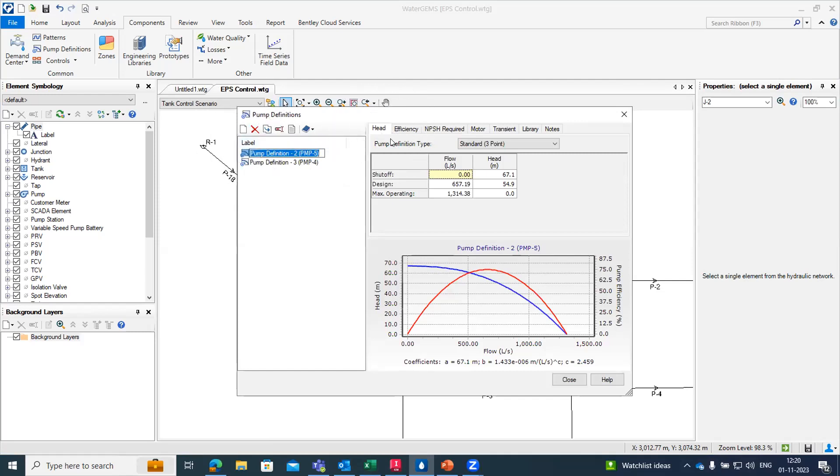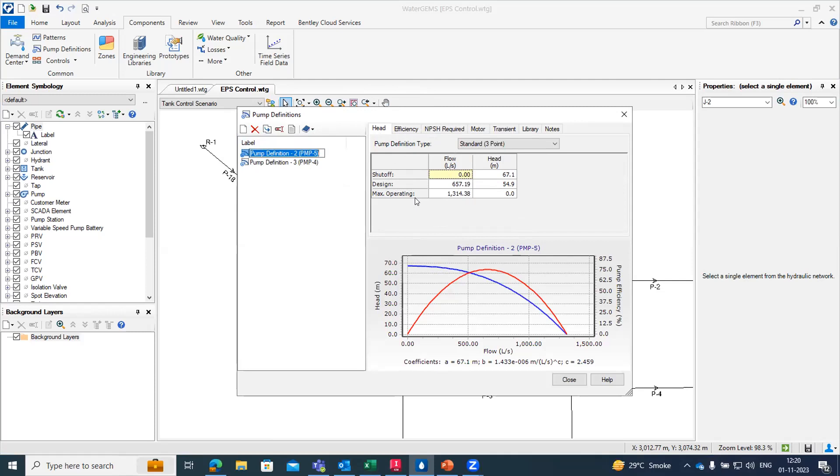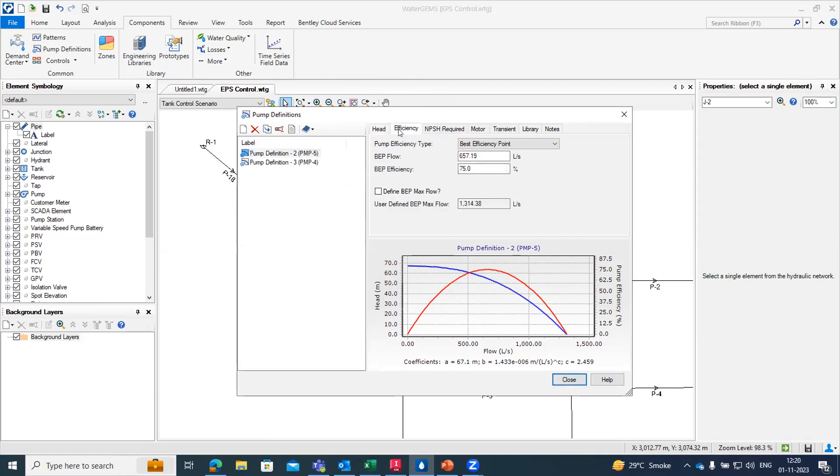Once we create a pump definition from this new tab, you can see the different inputs to be given. If you want to give the pump head we have to give shutoff head and then design flow, what would be my design head and how much will be maximum operating with respect to flow. If you want we can get efficiency as well like BEP flow which is best efficiency point flow or best efficiency point.